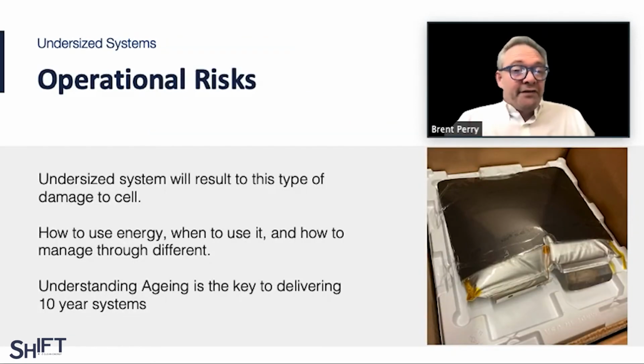Then you have to make sure you size the system correctly. Today, people are caught up in buying everything by the kilowatt hour without necessarily understanding the full operational risk they're taking on with that metric. The truth is every battery company delivers cells and systems with different performance capabilities. So the temptation to deliver a demand energy capacity without understanding how that's immediately impacted by the cells and battery you've designed is a risk we all run, making systems incorrectly sized for their applications, which ultimately forces them to age or fail faster and puts the cells at risk.